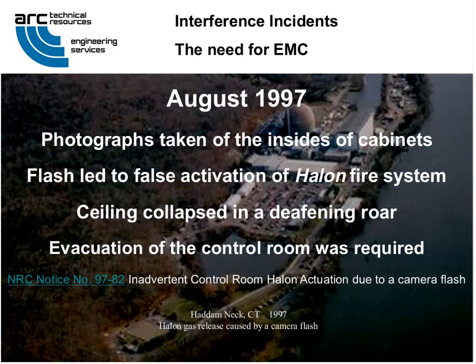In August of 1997, the operators at the Haddam Neck nuclear power plant ordered photographs to be taken of the inside of the control cabinets for training purposes. The flash photography of the control panel interiors led to the false activation of the halon gas fire suppression system. The ceiling collapsed when the fire suppression system fired in a deafening roar, forcing the evacuation of the control room, and a notice from the NRC.